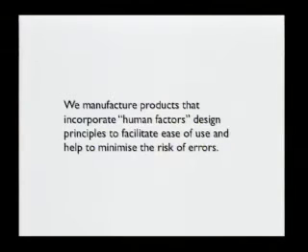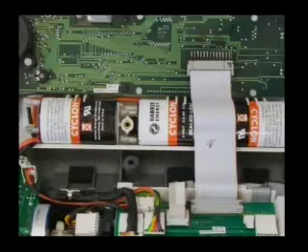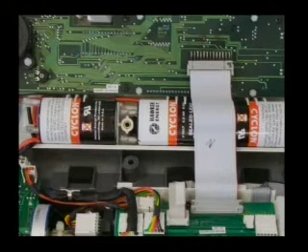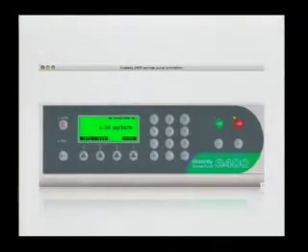Okay, I've got interested in syringe pumps, and I have reverse engineered a Graseby 3400 syringe pump, taken it to pieces, and I've got to know it really well. I wrote a Java program which simulates it, and I'll illustrate this program later. This is a screenshot of my simulation. I held the pump over a scanner, scanned it in, and then wrote a Java program, and when you press the buttons, it does more or less what the syringe pump does.